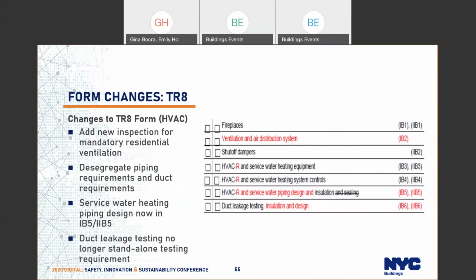All right, under the HVAC section on the TR8 form, we added a new inspection for a mandatory residential ventilation. So in the past, residential homes were only required to have exhaust ventilation. Now the Energy Code requires that they have either balanced ventilation or an ERV. And there's also an inspection component to this, almost like commissioning.